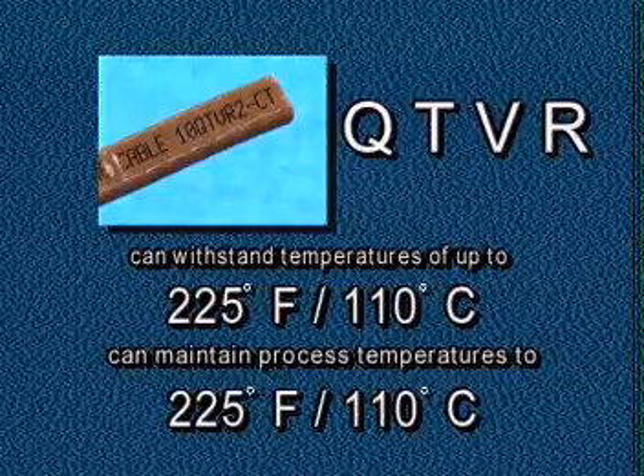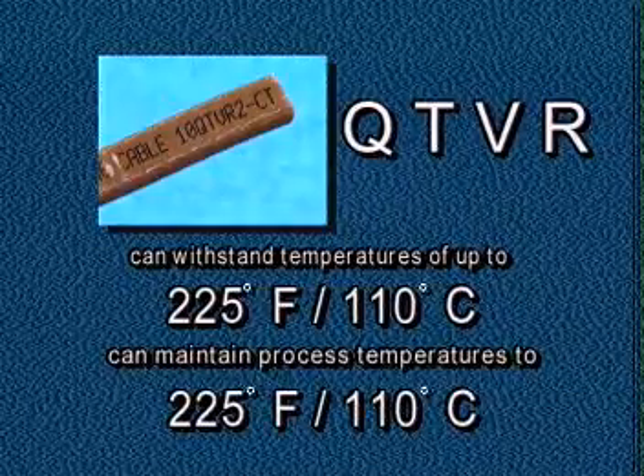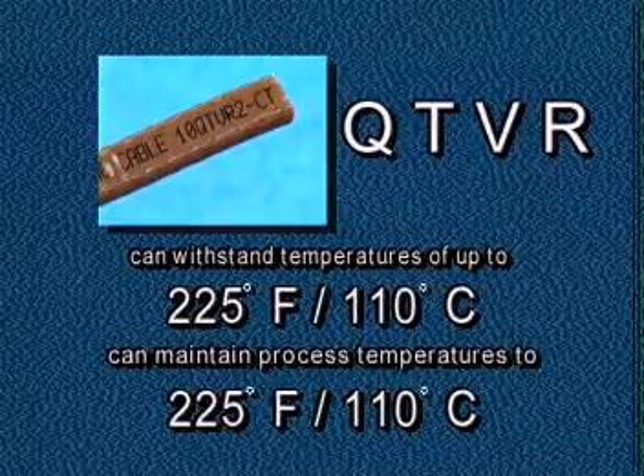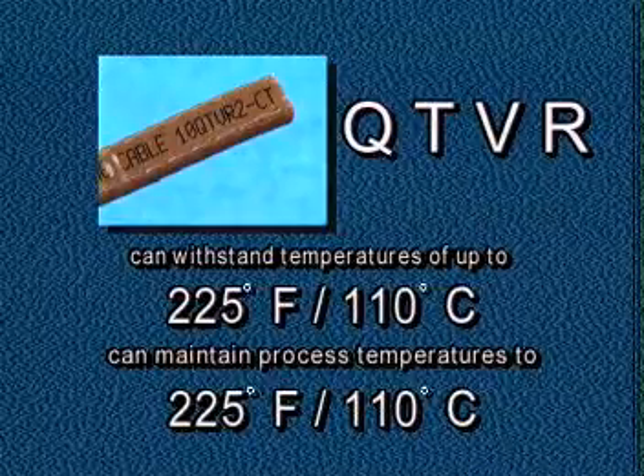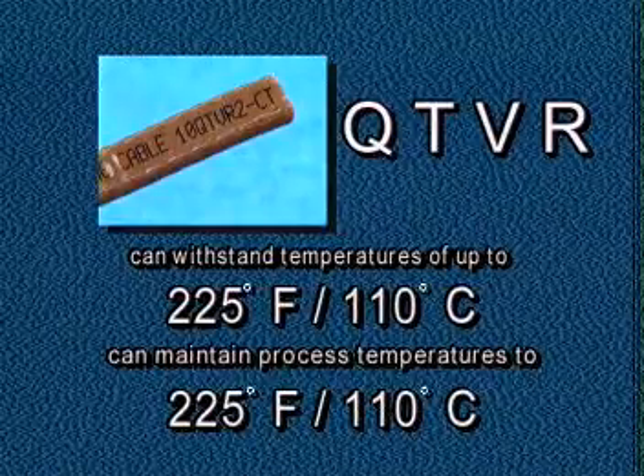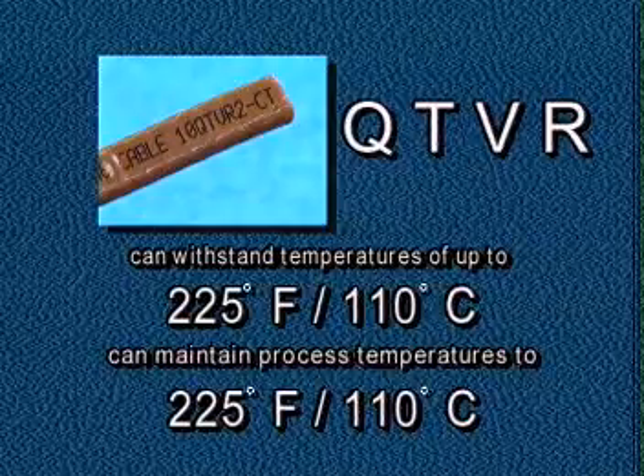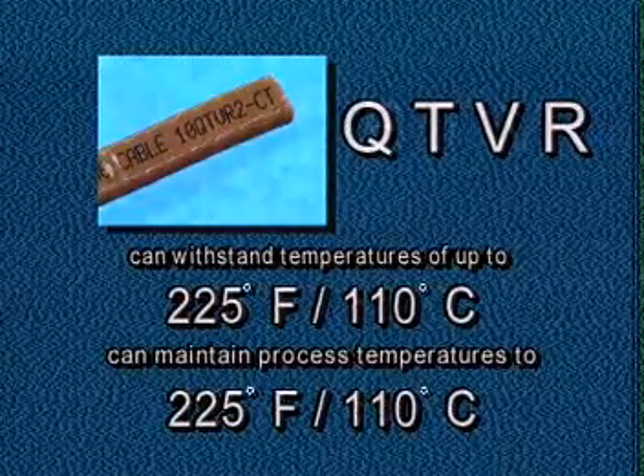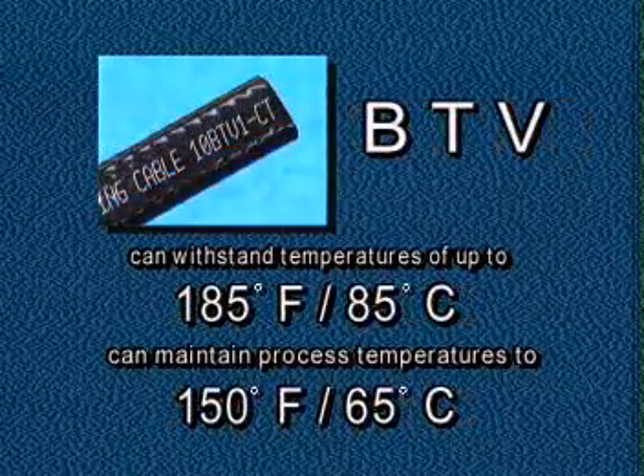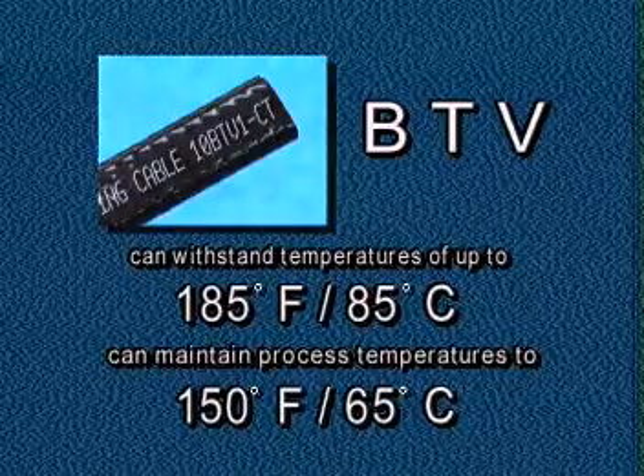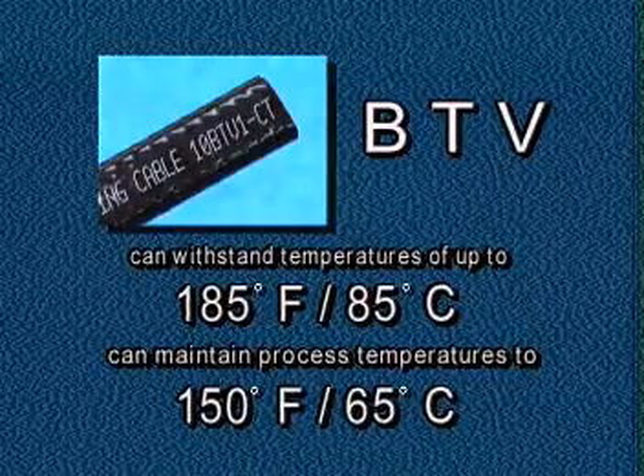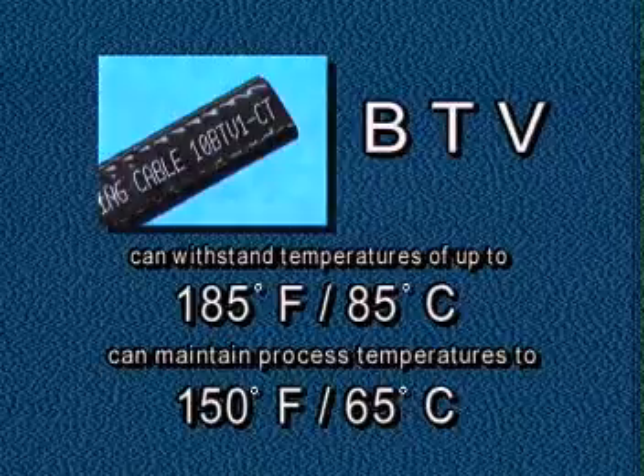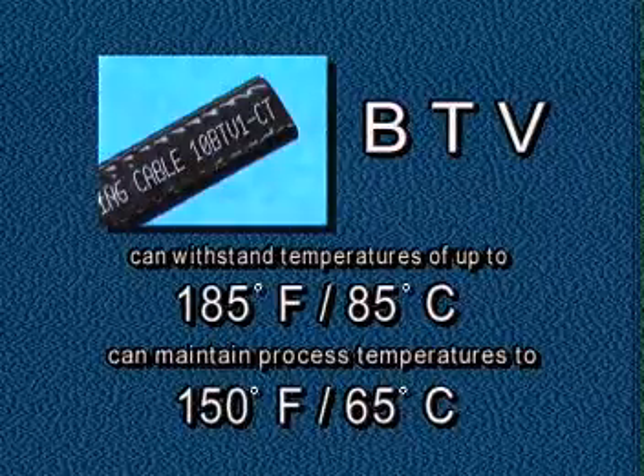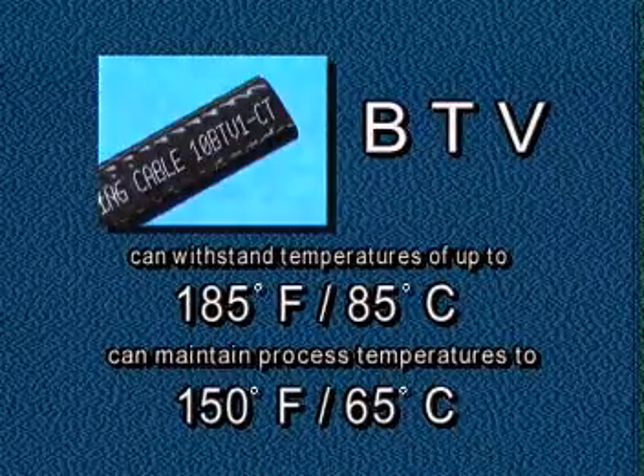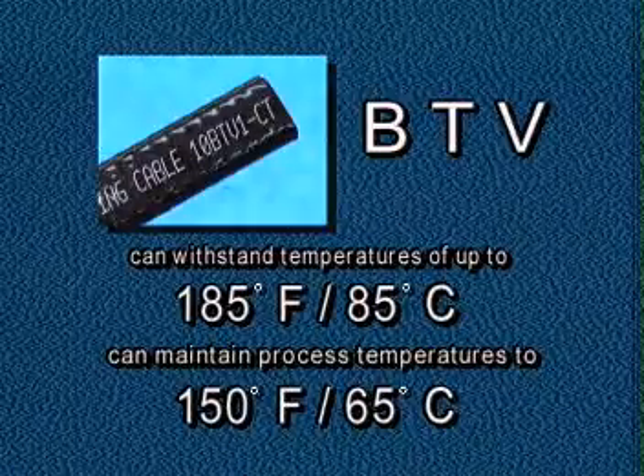QTVR cable can withstand temperatures of up to 225 degrees Fahrenheit or 110 degrees Celsius, and it can maintain process temperatures of up to 225 degrees Fahrenheit or 110 degrees Celsius. And BTV cable can withstand temperatures of up to 185 degrees Fahrenheit or 85 degrees Celsius, and it can maintain process temperatures to 150 degrees Fahrenheit or 65 degrees Celsius.